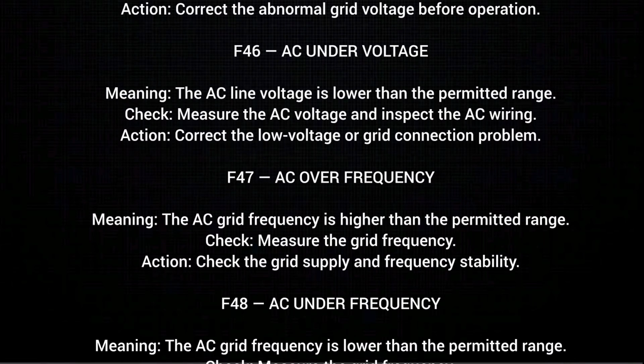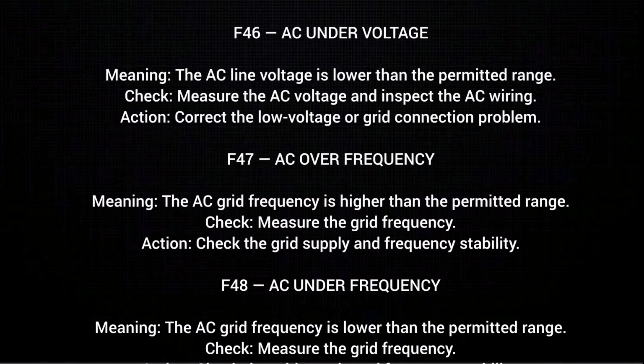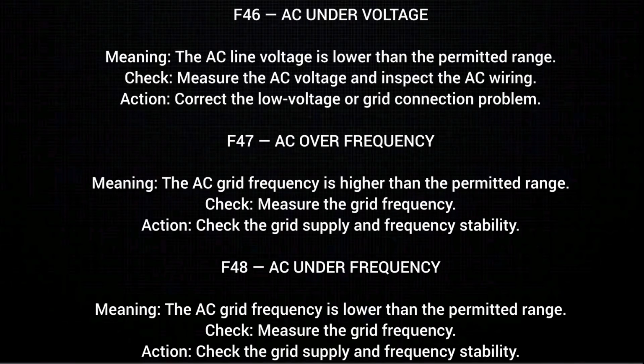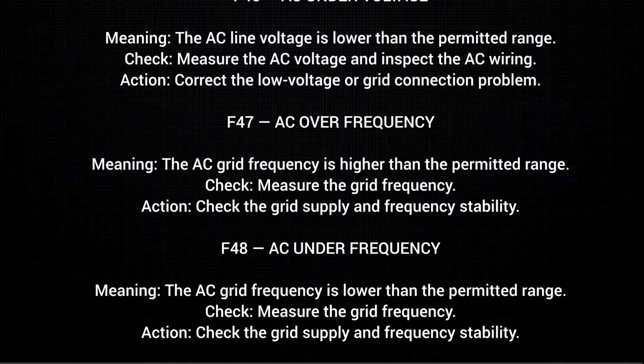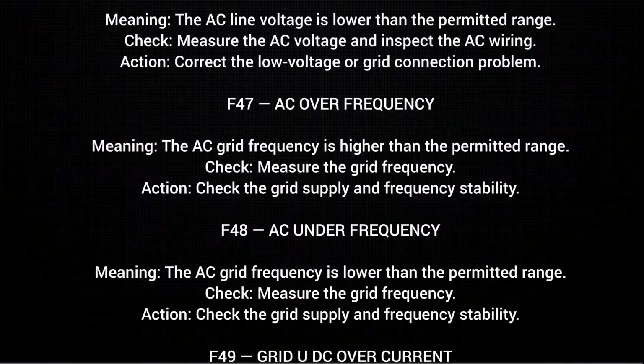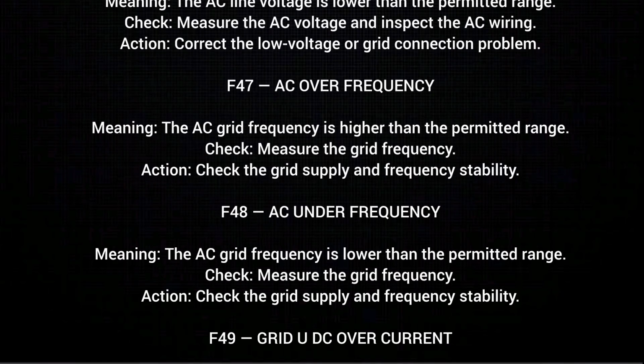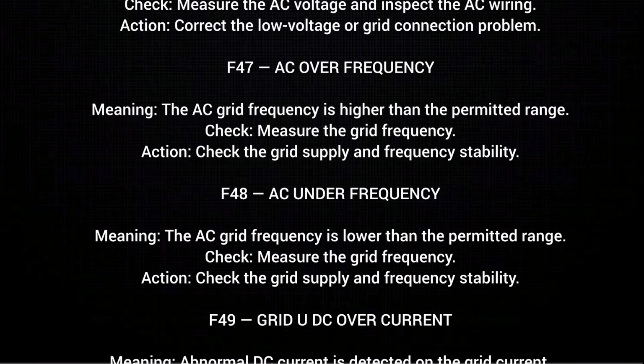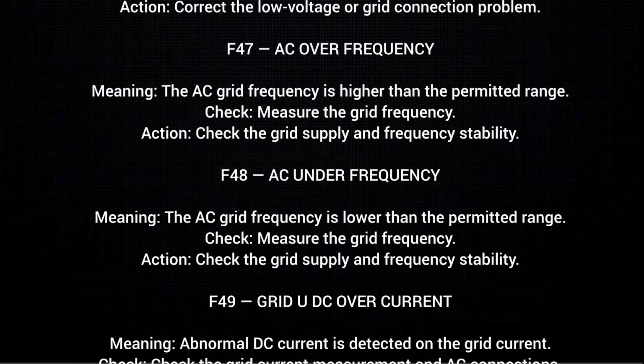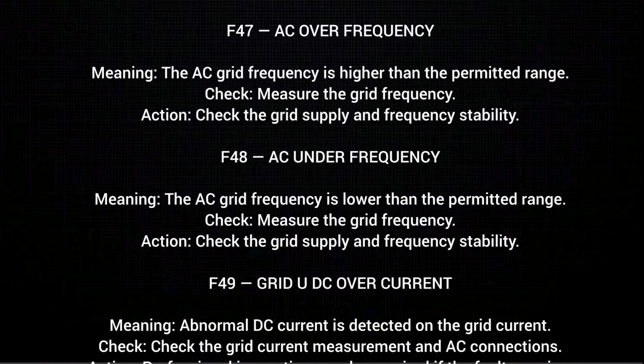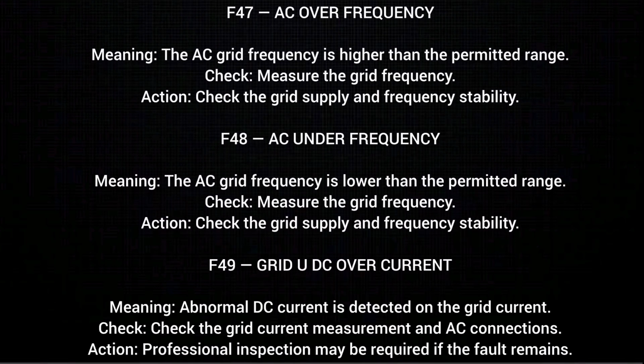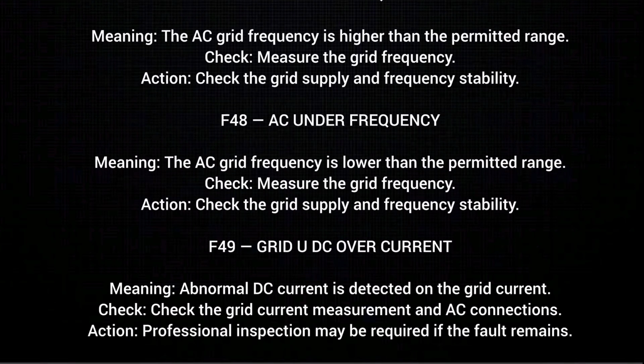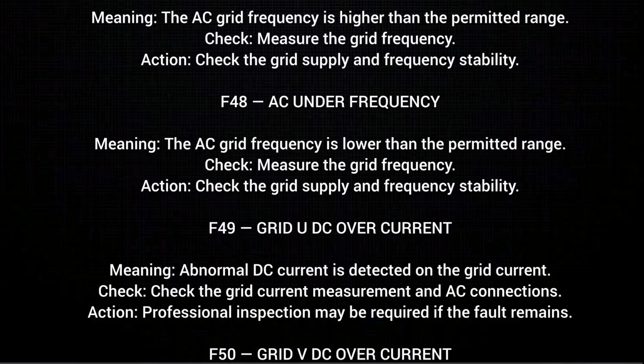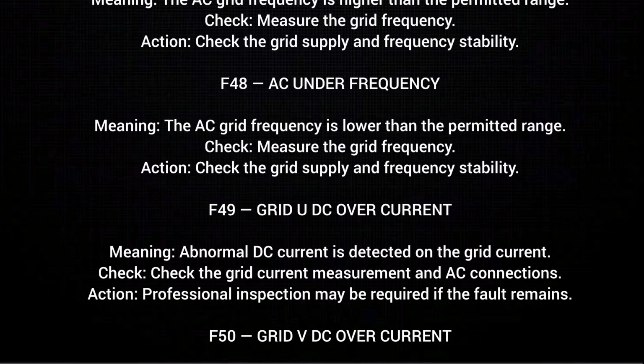F48. AC under frequency, meaning the AC grid frequency is lower than the permitted range. Check. Measure the grid frequency. Action. Check the grid supply and frequency stability. F49. Grid UDC overcurrent, meaning abnormal DC current is detected on the grid current. Check. Check the grid current measurement and AC connections. Action. Professional inspection may be required if the fault remains.